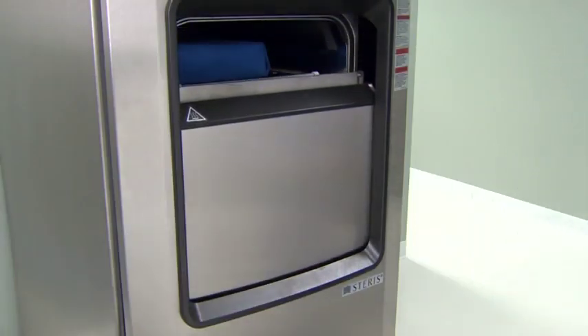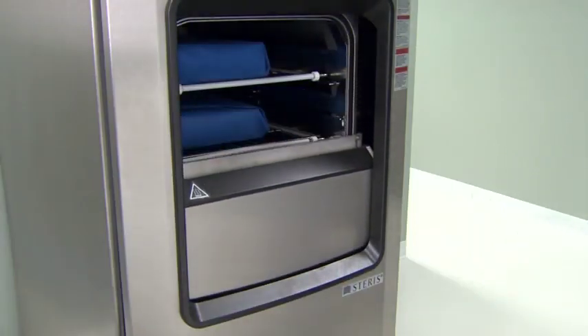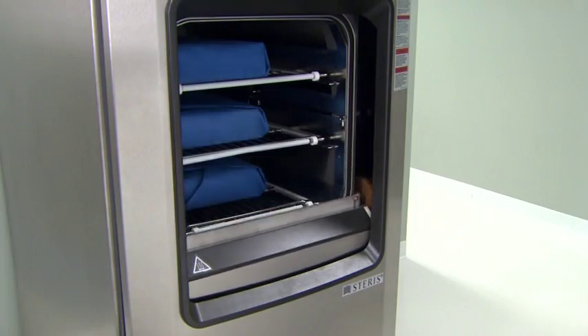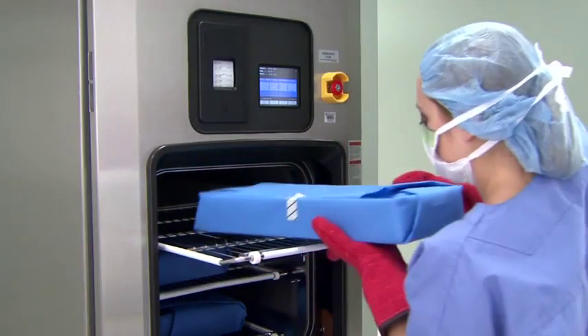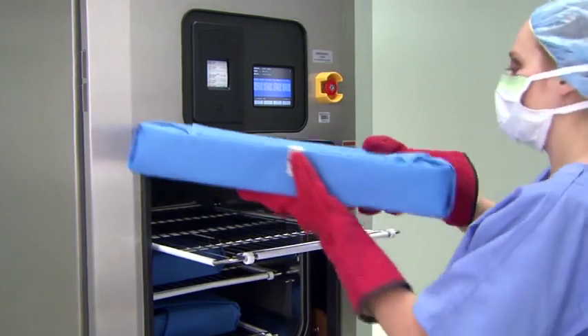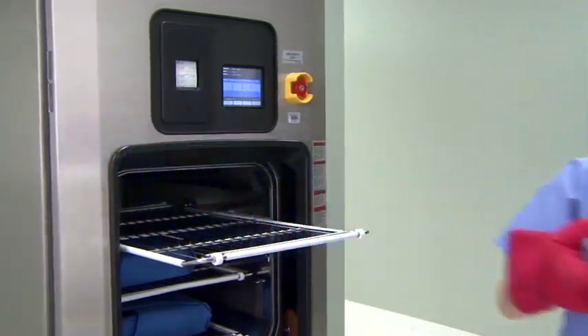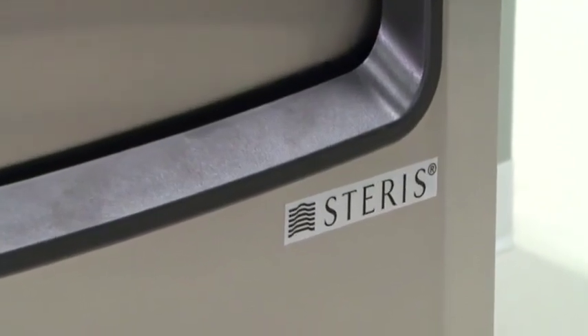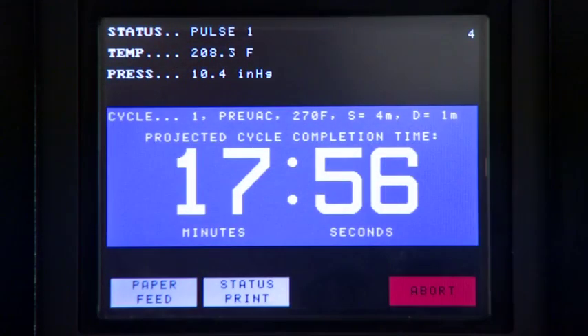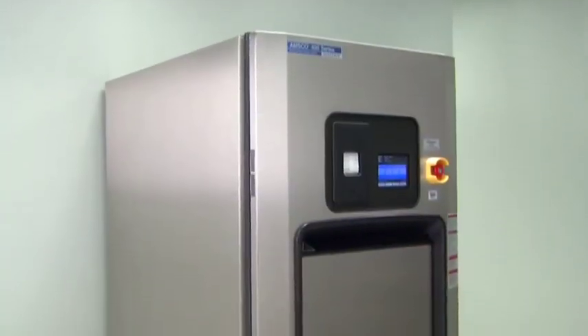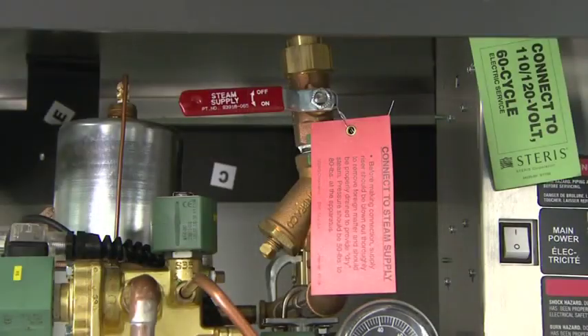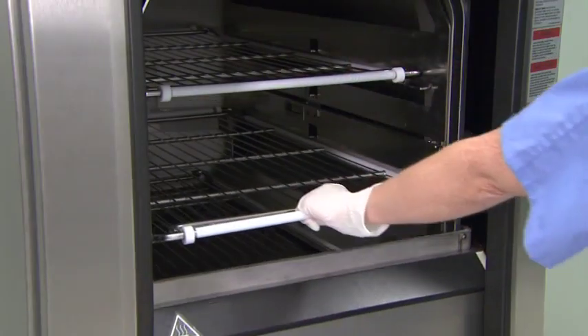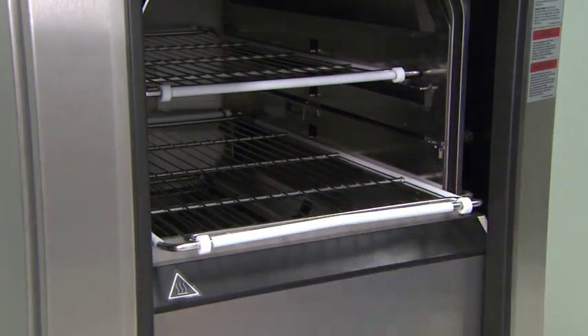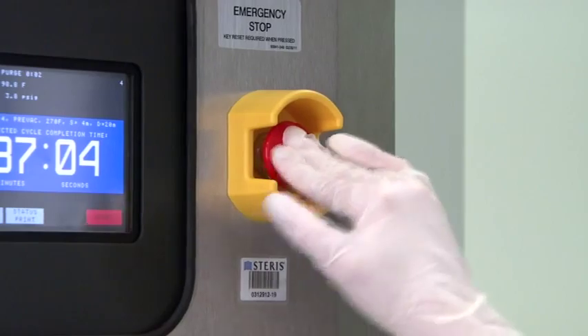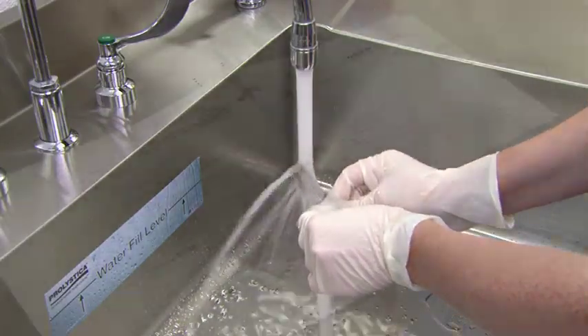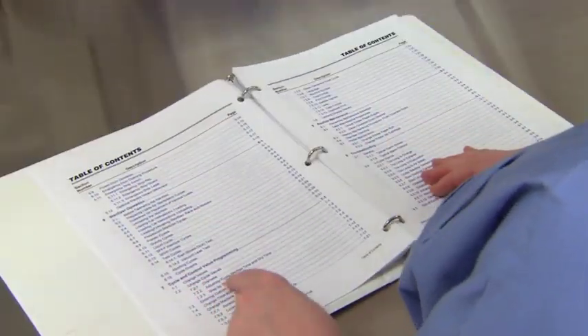After sterilization, goods should be stored in conditions that will not compromise the barrier quality of their wrapping materials. Be sure to understand and follow your department's policies and procedures regarding the processes involved with these steps. Safety, yours and the patient's, is an important part of the sterilization process. AMSCO 400 Series sterilizers include a number of important safety features. Be sure to read all of the safety warnings and cautions that are detailed in the safety precautions, sterilization operation, and routine maintenance sections of your 400 Series operator manual.